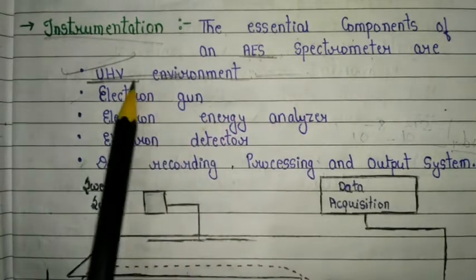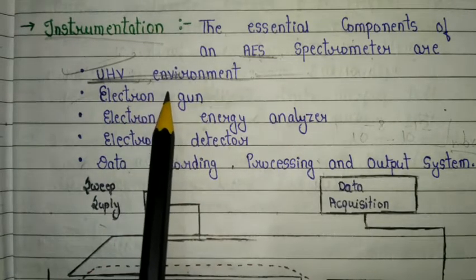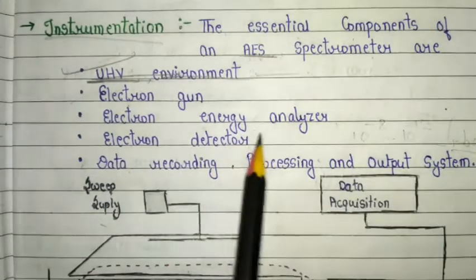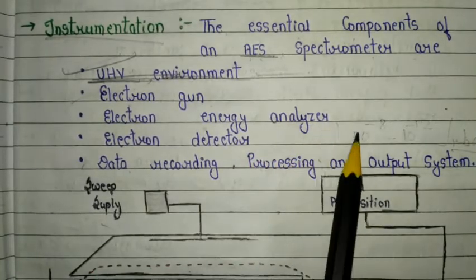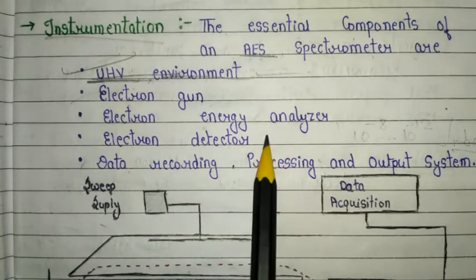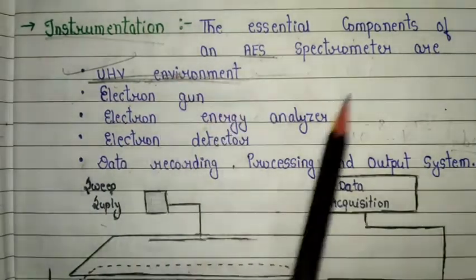The first essential component is the UHV environment — UHV stands for Ultra High Vacuum. It is characterized by a pressure lower than 10⁻⁸ to 10⁻¹² mbar. It is very important in scientific research because experiments often require a chemically clean sample surface with the absence of any unwanted adsorption.